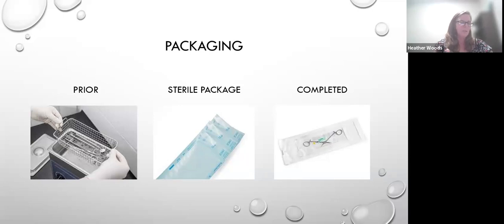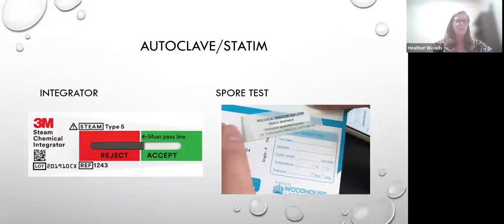And they also mentioned, again, if they don't use reusable equipment, they don't have to have a sterilization room. A lot of facilities are doing that as well. So I mentioned the integrator strips. These go in with each cycle. The integrator is a test or a device designed to validate one or more of the following criteria, like Michael mentioned: time, temperature, steam, and pressure. These types of integrators can be chemical, biological, mechanical.